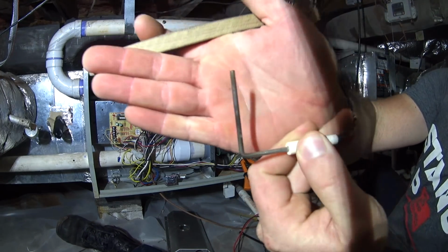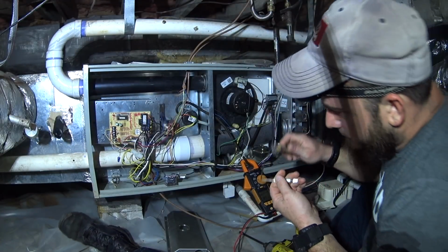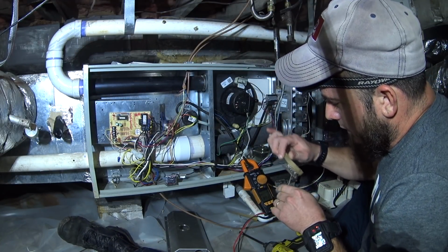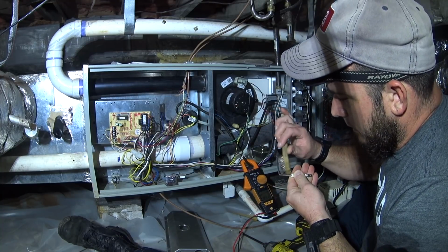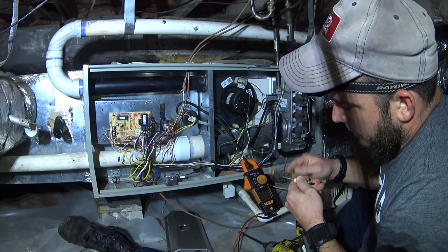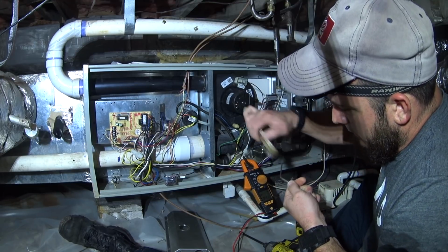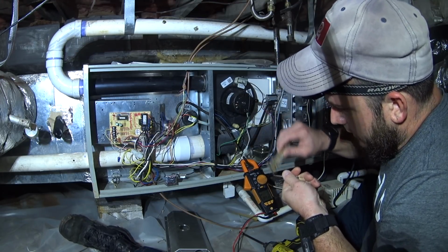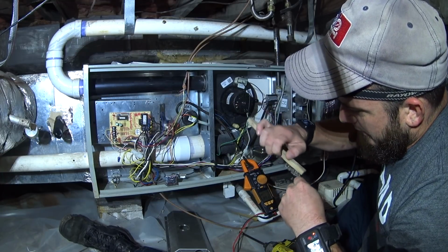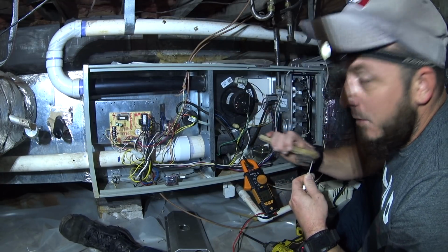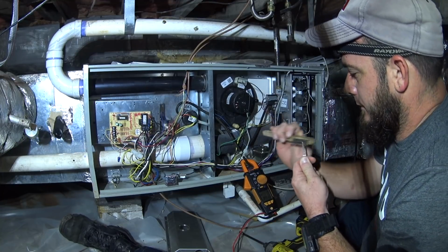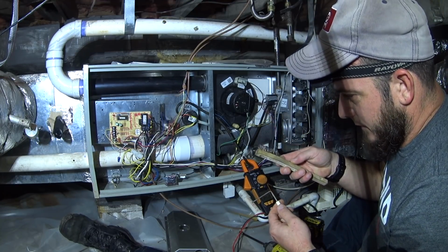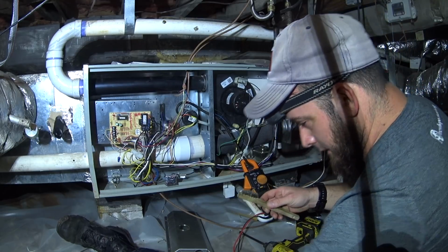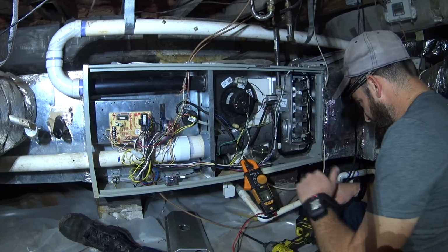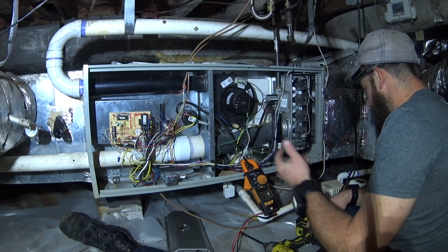Flame sensor looks kind of grody. Once again, you probably can't see it very well, but we're taking the soft bristle brush and taking the buildup off of the flame sensor. You want to do it gently and use a soft bristle brush. Brass bristles work nicely, though I couldn't find those, so this one's, you know, I don't know, wire bristle. It's soft and I'm not hitting it real hard to damage anything.